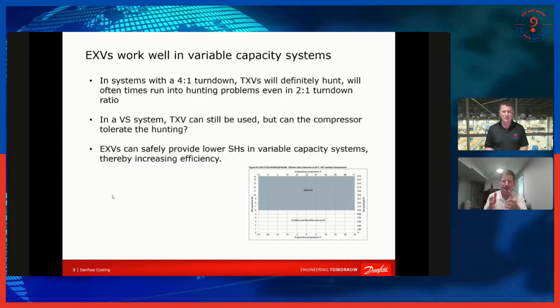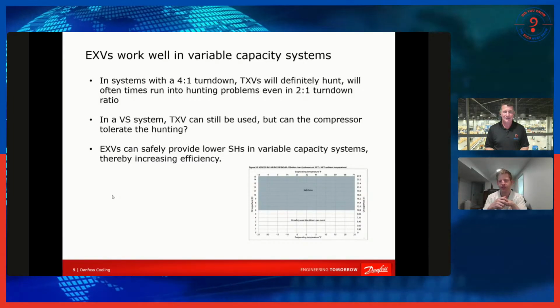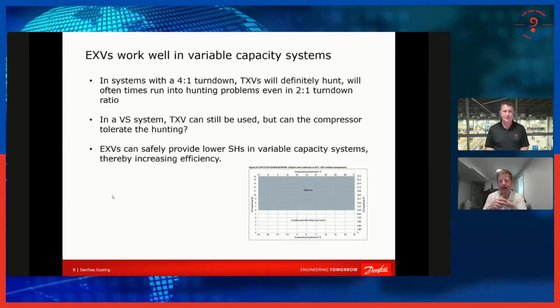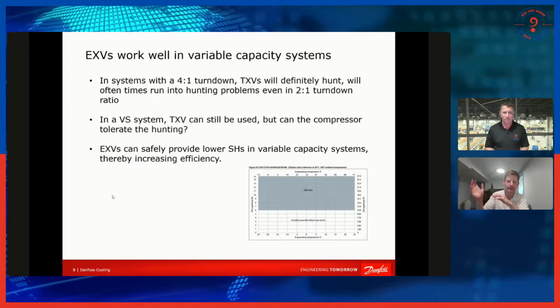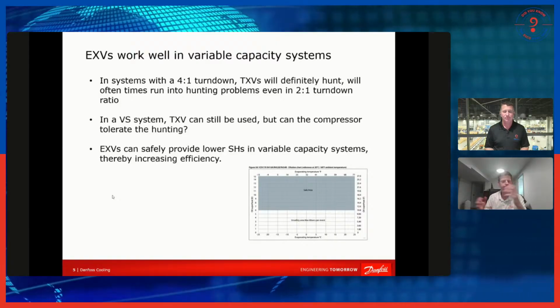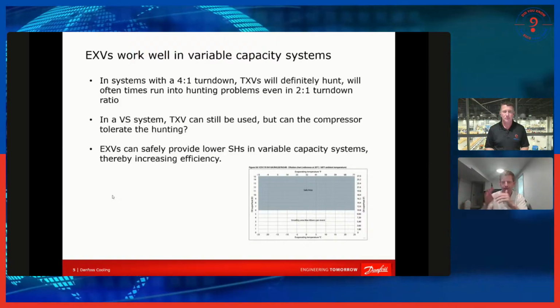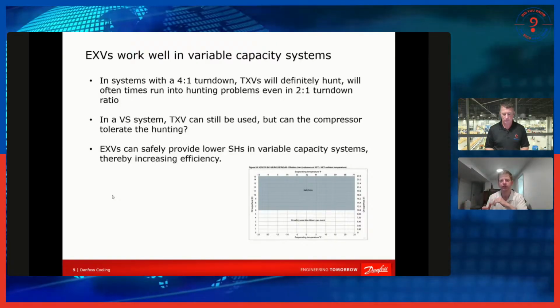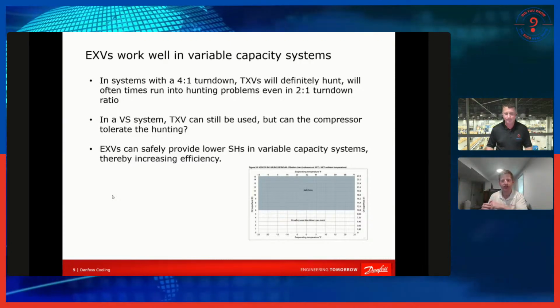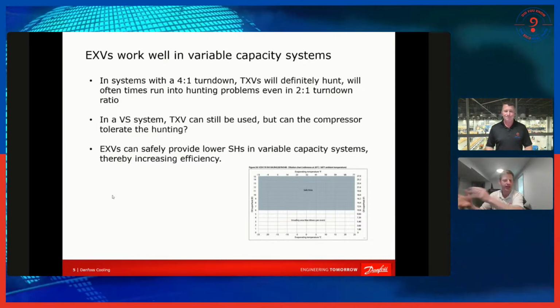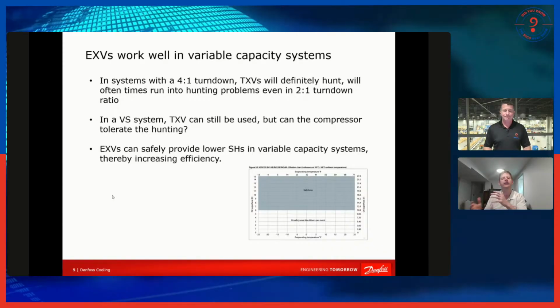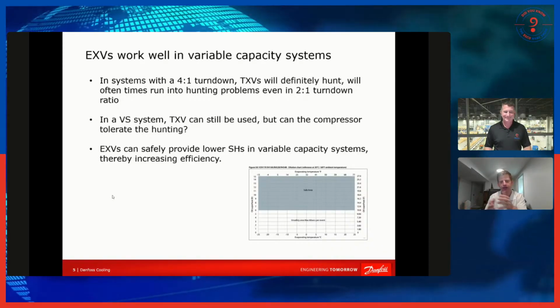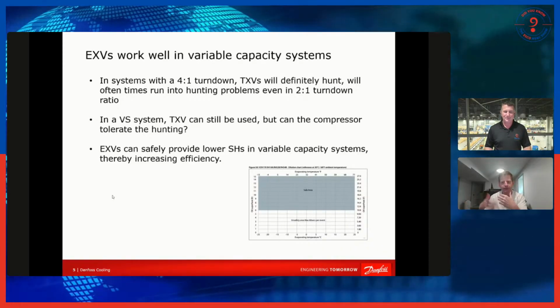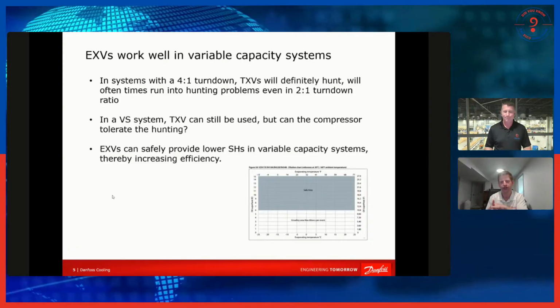A TXV by itself in a supermarket case is going to be cheaper than having to get a case controller and the driver and the EXV and the sensors. But more and more in these cases, they want to make them dual temperature and things like that. So there's already a lot more electronics in there anyway. So if you already have a lot of electronics in there, it doesn't make it quite as expensive to add in that EXV compared to a TXV. And then you can take advantage of some of those control advantages.